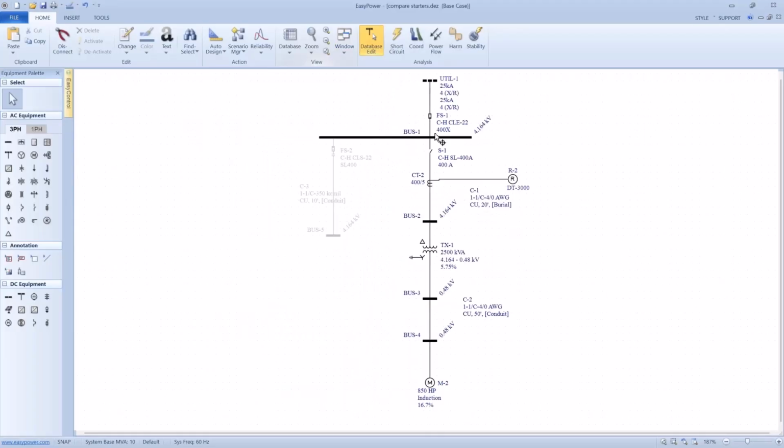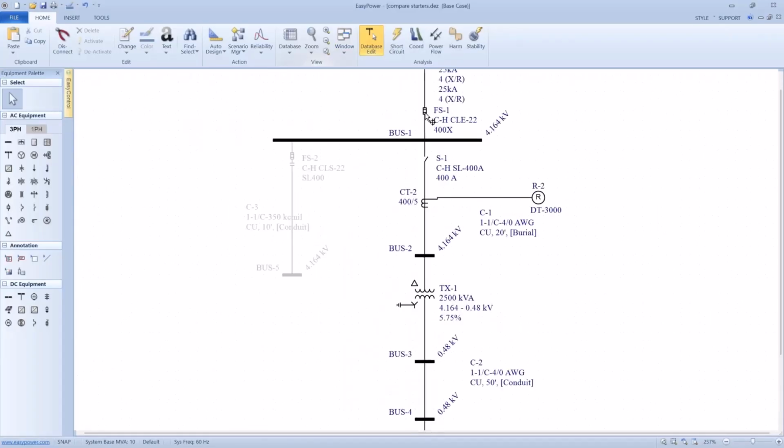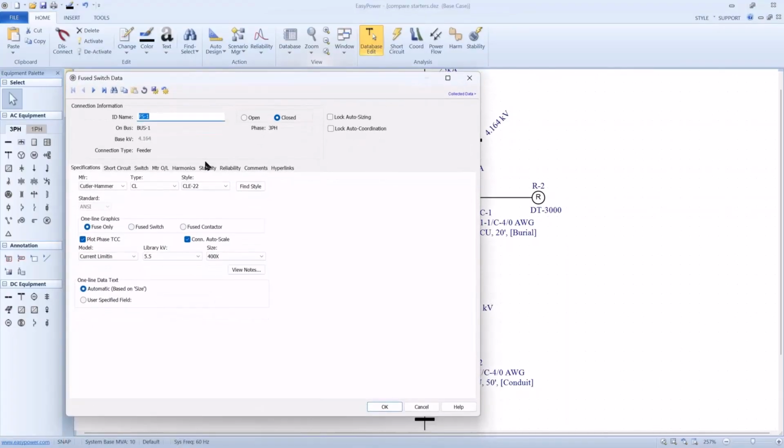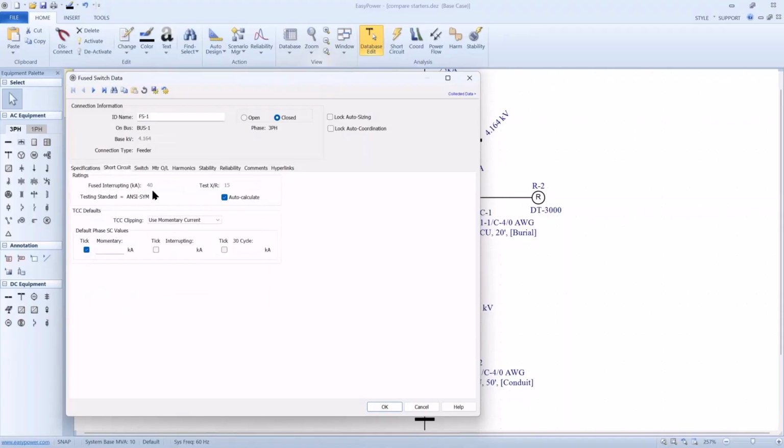What it amounts to is that, based upon the data sheets for the Ampgard series, the application note claims that if we use a Cutler Hammer CLE-22 400 amp fuse in our circuit, it will afford us higher protection for downstream devices.